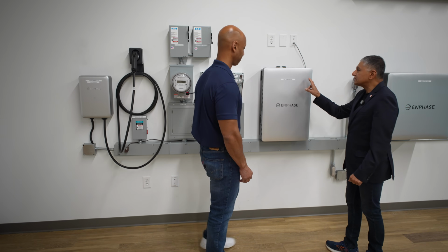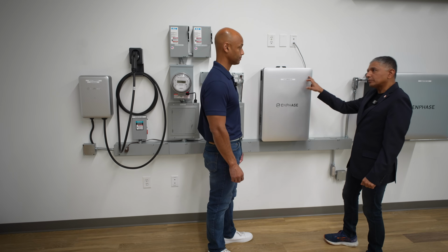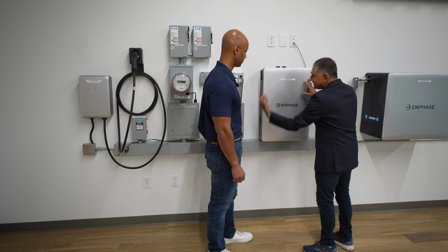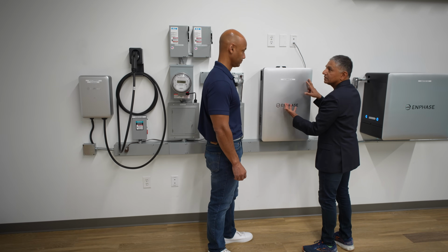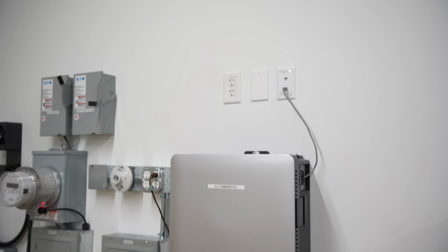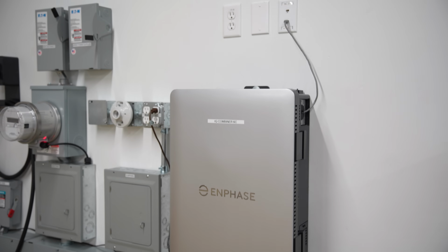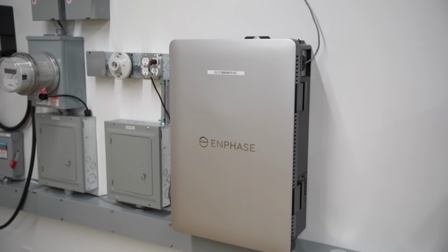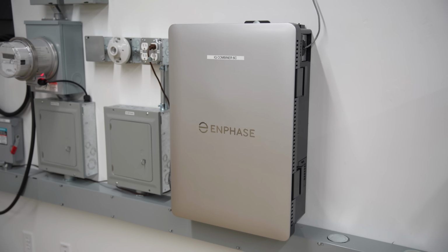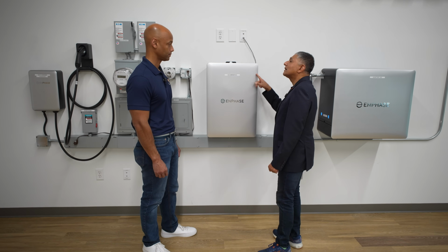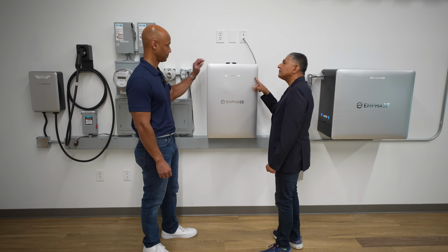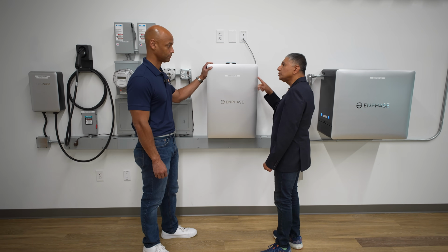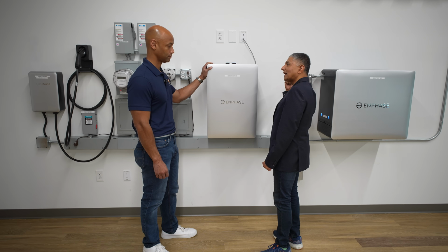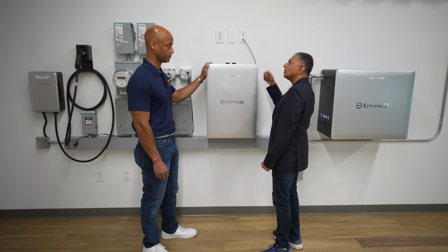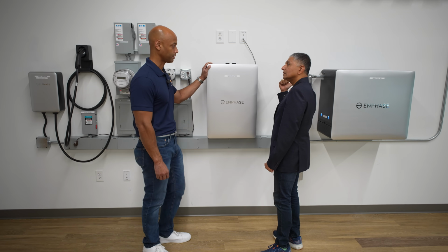Okay. With the Combiner 6, obviously the output of this, which aggregates all the DERs, the distributed energy resources, your solar, your battery, even your EV charger, etc., now lands in the main panel, right? Regardless of whether it's a 100 amp main panel or a 200 amp main panel, you can land up to 100 amps of current from this device onto the main panel.